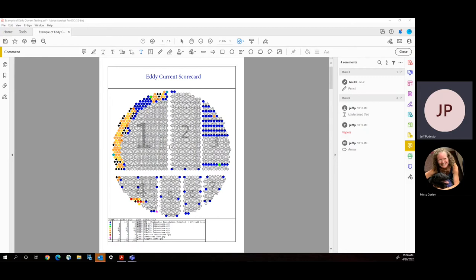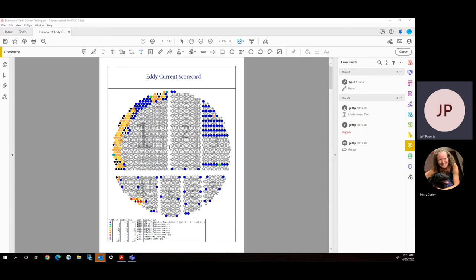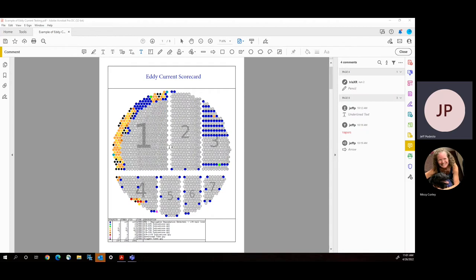I'm going to leave that up for now, and then I'm going to take you through a test. I'll just give you a little feedback on eddy current testing. I think we all know that finding leaks in an evaporator usually means it's an after-the-fact situation where we've got product that's showed up in the condensate, and then we know that we have tubes leaking. That leads us to having to do repair, which is even worse because that usually means we've got to shut down, clean the evaporator. We've got to plug the bottom of the tubes, fill those tubes with water, and see which ones leak out, and then plug those tubes off so that they don't negatively affect the operation of the evaporator going forward. What we're left with, though, is why did this tube leak, and where is the next tube that's going to leak coming from?